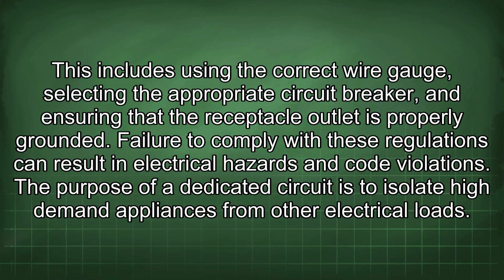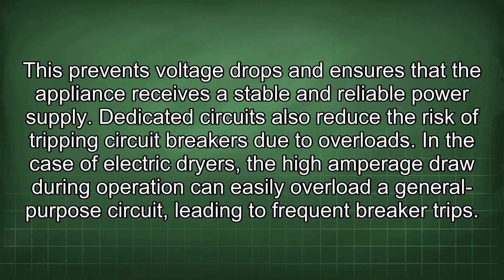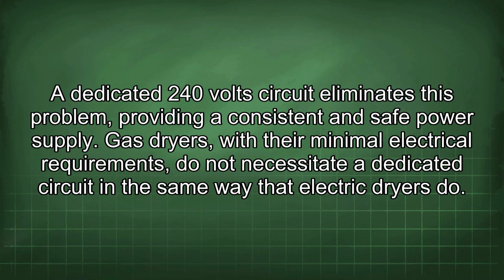The purpose of a dedicated circuit is to isolate high-demand appliances from other electrical loads. This prevents voltage drops and ensures that the appliance receives a stable and reliable power supply. Dedicated circuits also reduce the risk of tripping circuit breakers due to overloads. In the case of electric dryers, the high amperage draw during operation can easily overload a general-purpose circuit, leading to frequent breaker trips. A dedicated 240 volt circuit eliminates this problem, providing a consistent and safe power supply.